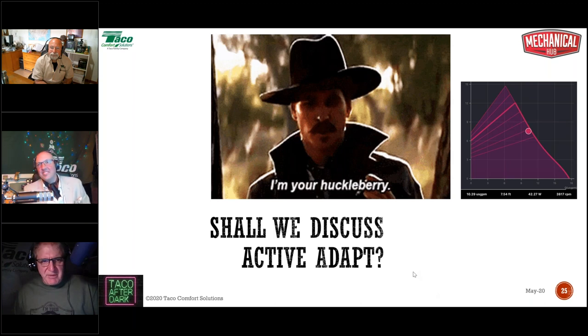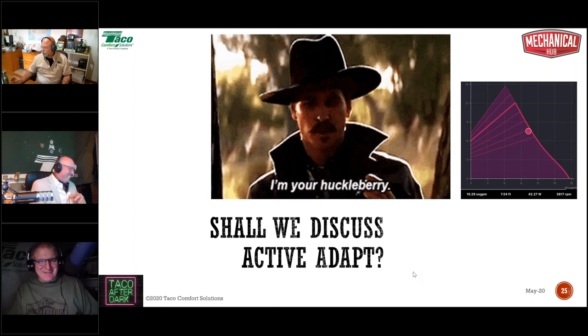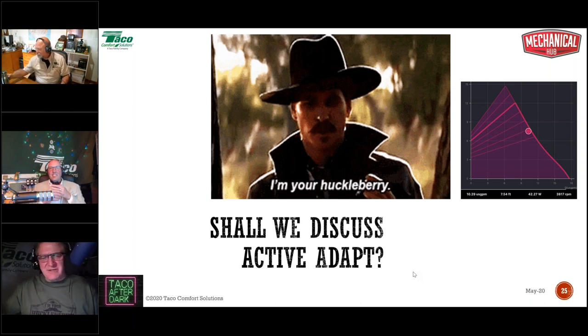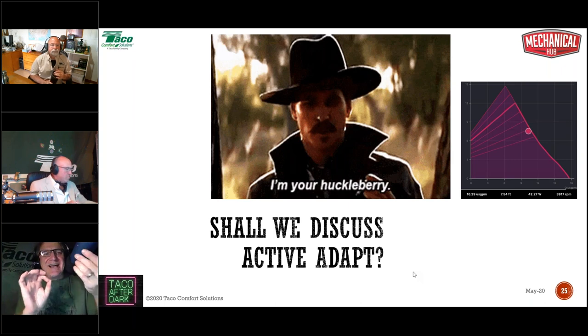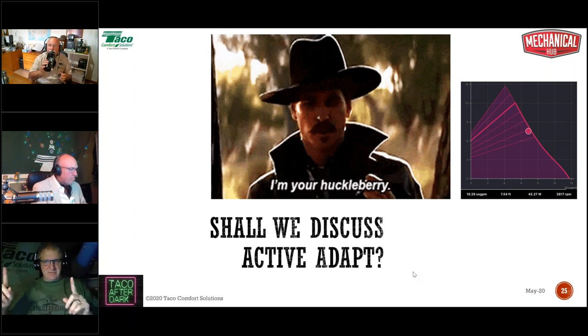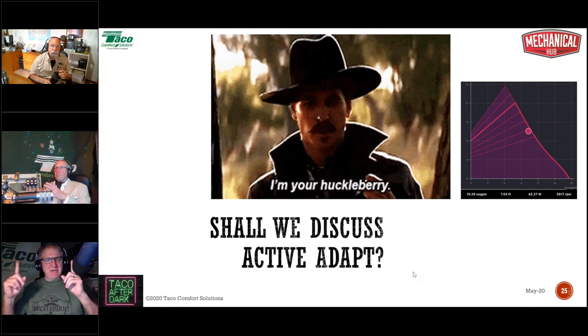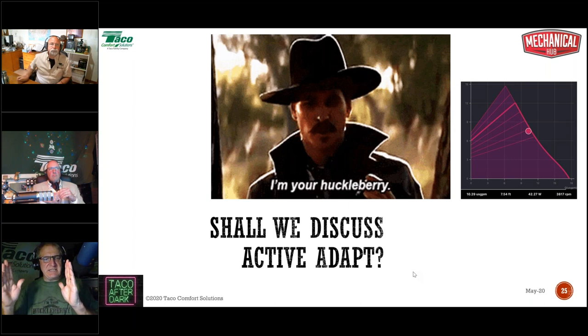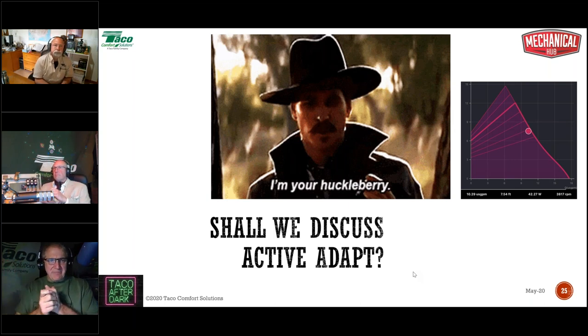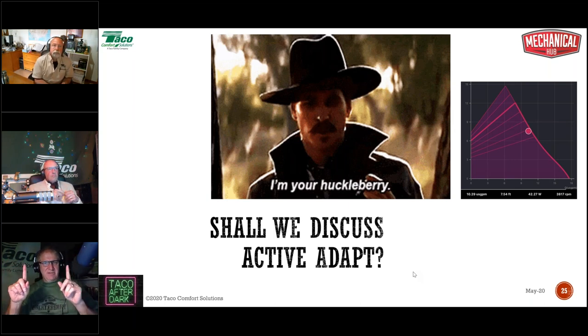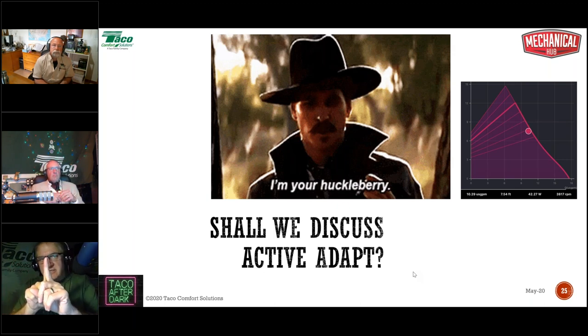Well, here's a good question. Does it pay to spend money on delta T as opposed to delta P? Andrew, that's a great question. And the answer is, it depends. It really depends on the size of the system. The bigger the system, the bigger the difference, because you're going to have more variable speededness with a delta T pump on a bigger system. As systems get smaller, the difference starts to get closer and closer to the point where maybe there's very little difference at all.